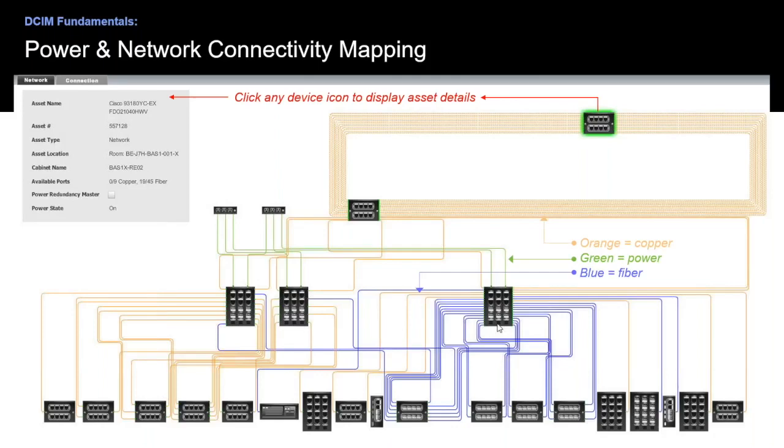And when we were looking at tools, one of the things we understood was that once you've gone beyond just assets, which are already difficult enough to maintain all the records on, the life cycle, et cetera, going down to power level as the next step we had taken has added that, times 10, in terms of the number of connections you have to be able to track and validate so that you can do maintenance such as cutting off your A or B side power, and recognizing if there is something that's exposed to a single corded device, et cetera, so that you can alert someone to the fact that it will go down or have it shifted over.